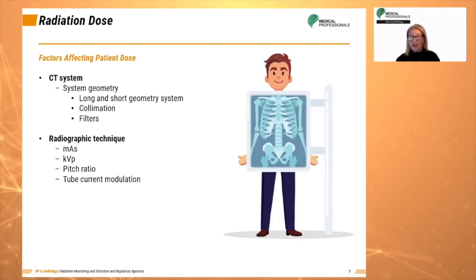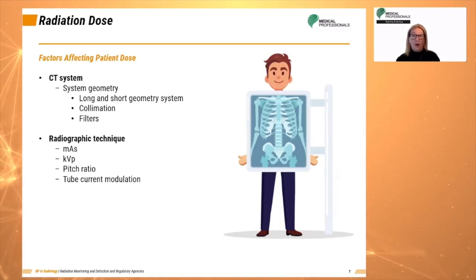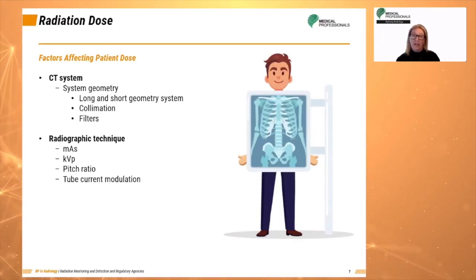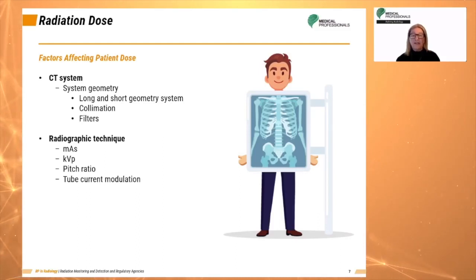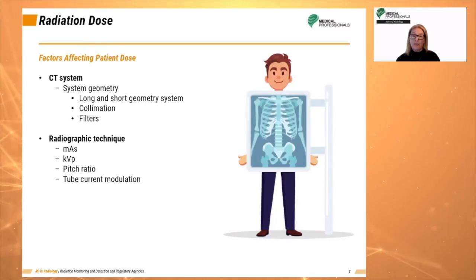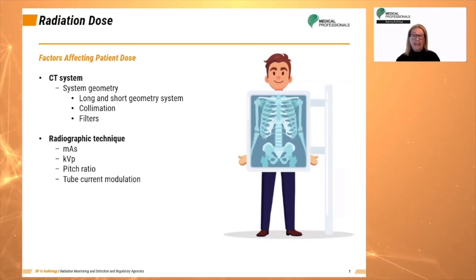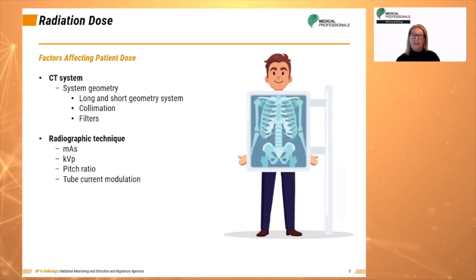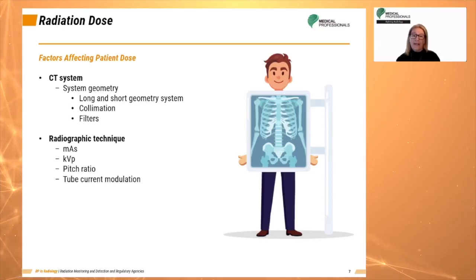Tube current modulation regulates the pulse of current through different body tissues. It reduces overall radiation dose to the patient and allows sufficient photons to pass through the widest parts of the patient without unnecessary dose to the narrower parts. The purpose is to maintain a near-constant signal-to-noise ratio across different areas of the body with varying thicknesses, avoiding excessive radiation doses while maintaining image quality.